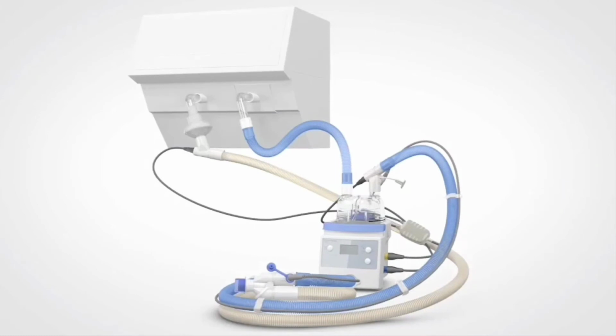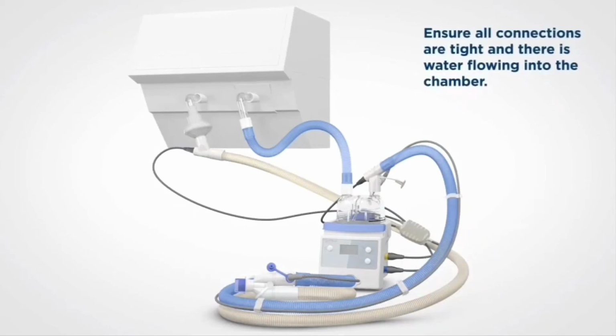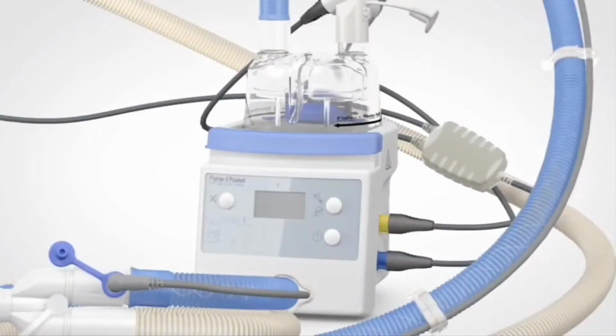When you're ready to use the humidifier, ensure all of the connections are tight and that there is water flowing into the chamber. Turn the device on by pressing the On Standby button in the bottom right of the control and display panel. When the device is turned on, it will be in invasive mode. We'll discuss how to change modes and troubleshoot any setup alarms later.